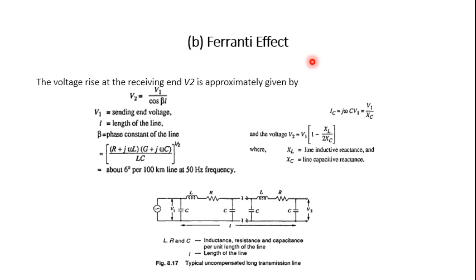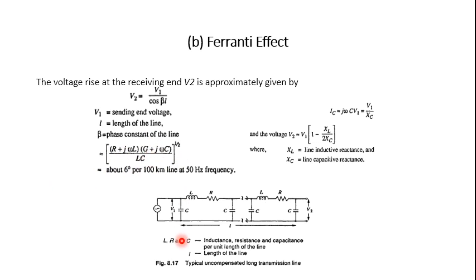Next is the Ferranti effect. For a long uncompensated transmission line, there is a voltage rise at the receiving end. The receiving end voltage V₂ is approximately given by: V₂ = V₁ / cos(βl), where V₁ is the sending end voltage, l is the length of the line, and β is the phase constant of the line.